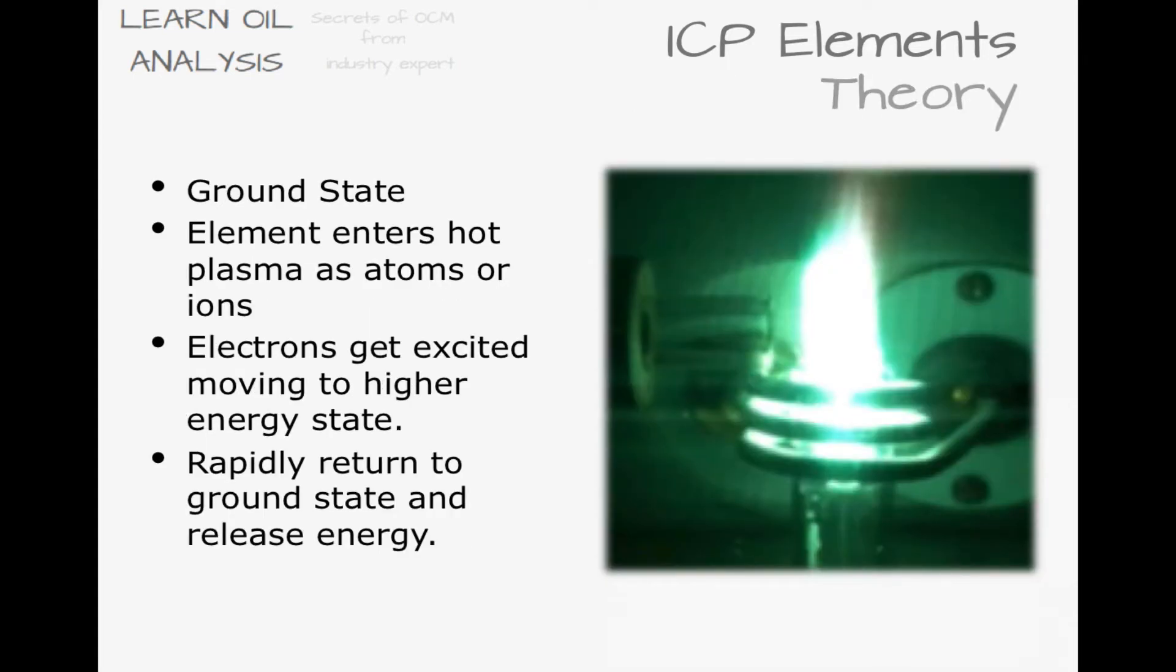The theory of ICP is that an element in its ground state enters the hot plasma where its electrons get excited and move to a higher energy state. This higher energy state is not stable and the energy is quickly released as a wavelength of light, specific to each element. The higher the intensity of each element specific wavelength, the higher the concentration of the elements in that sample.